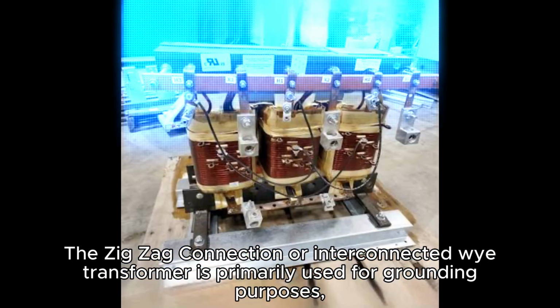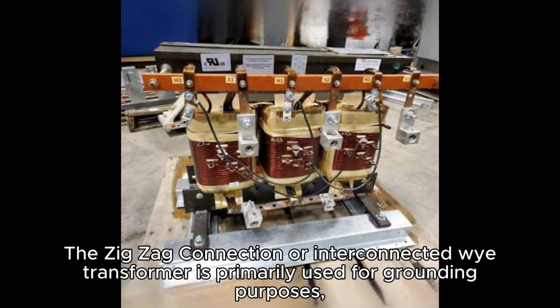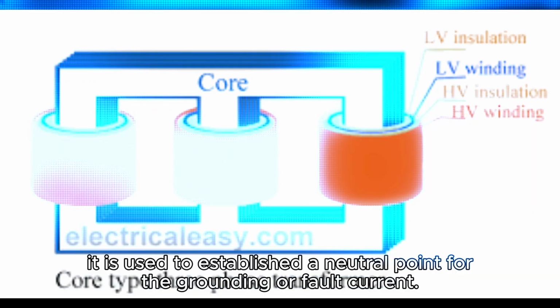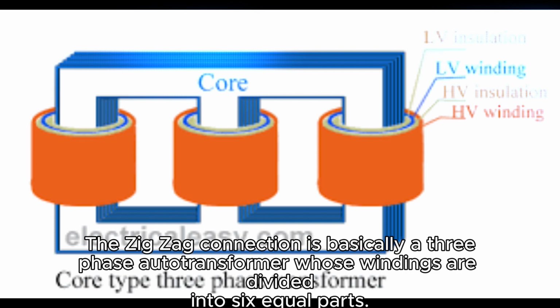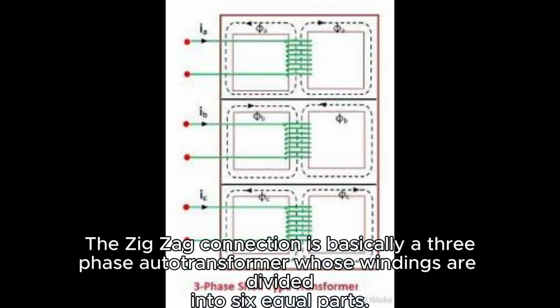The zigzag connection, or interconnected Y transformer, is primarily used for grounding purposes. It is used to establish a neutral point for the grounding or fault current. The zigzag connection is basically a three-phase autotransformer whose windings are divided into 6 equal parts.